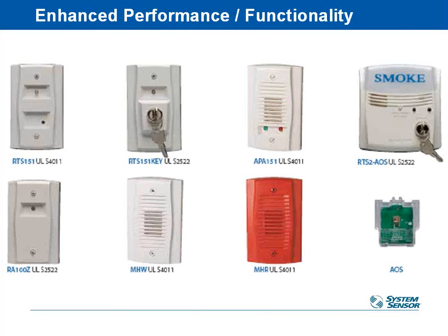There are numerous remote test stations and alerting stations available for these products, like with most manufacturers. So for example, if I just have the need to have a remote indicator, this bottom left one has an indicator light on it that can tell me if I have a problem with my detector. The top one has 2 indicator lights on it, so I can have one that says, do I have good power and or do I have a problem? There's one with key switches to put them into a test mode so the firemen can do that. There's ones with LED lights and horns on them. There's ones with just horns. They come available in white or in red, depending on what you're trying to do. And then there's the full one I just showed you with the strobe light and the horn and the test station and the key. So everything in one.